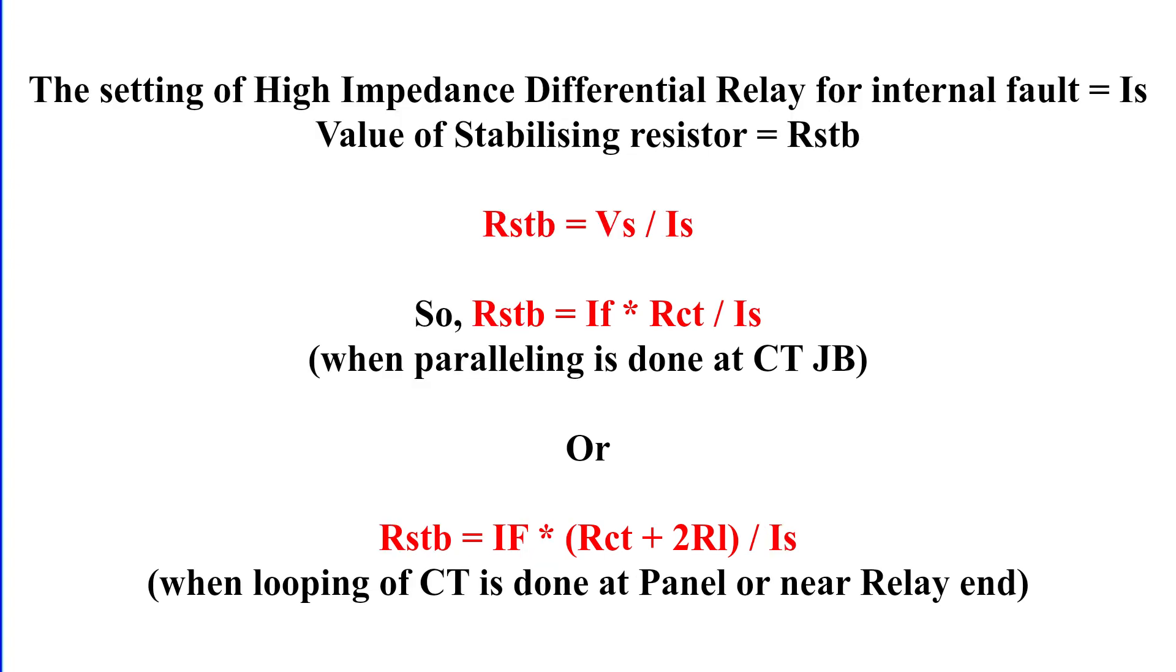Now, let's determine the value of the stabilizing resistor. The relay has a set current value, IS, for internal faults. To prevent false operation during through faults, the voltage across the CT should not drive a current greater than IS through the relay. Thus, we place a stabilizing resistor, RSTB, in series with the relay coil. The value of RSTB is calculated as RSTB equals Vs divided by IS.